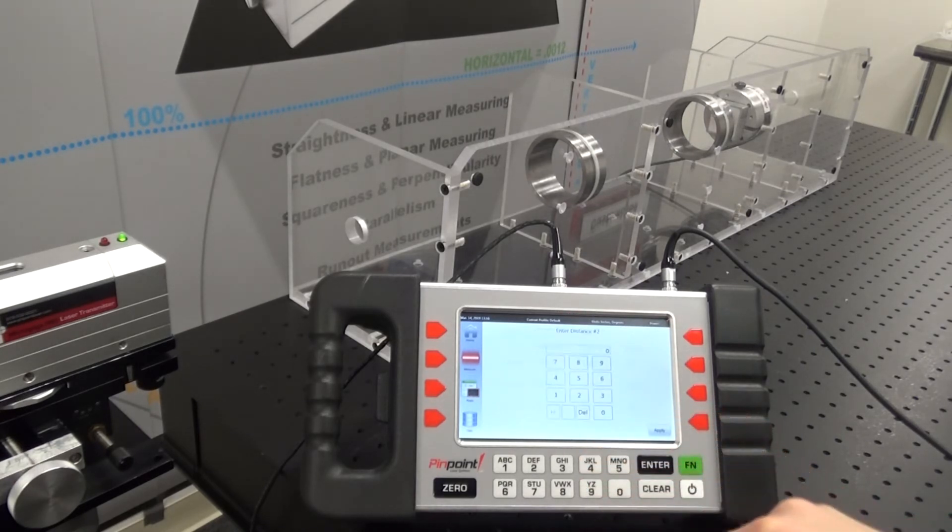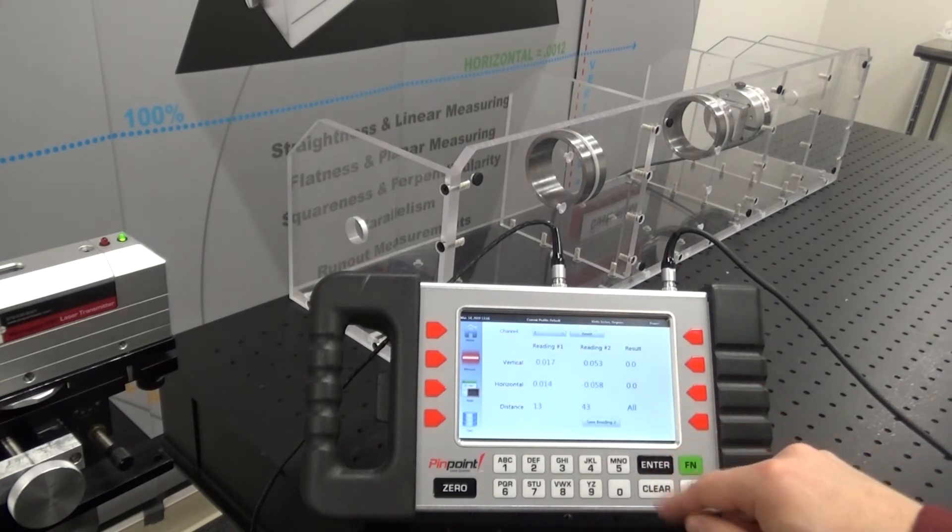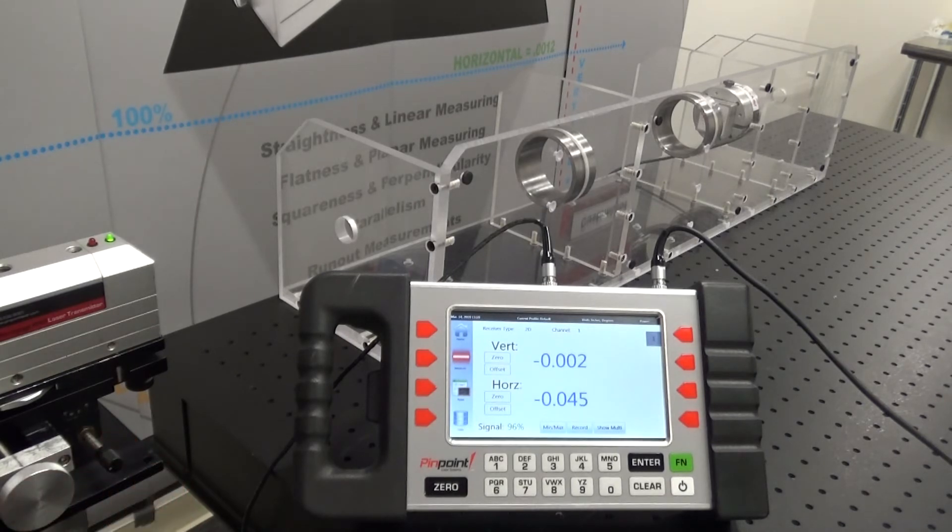the operator will be instructed on where to aim the laser using the pitch and yaw knobs of the 4-axis mount. In this example, the display calculates that the laser needs to be aimed at negative two vertical and minus 45 thou horizontal to achieve a straight line through the bores. So we adjust the pitch and yaw knobs of the 4-axis mount accordingly until the laser is aimed at these target values.